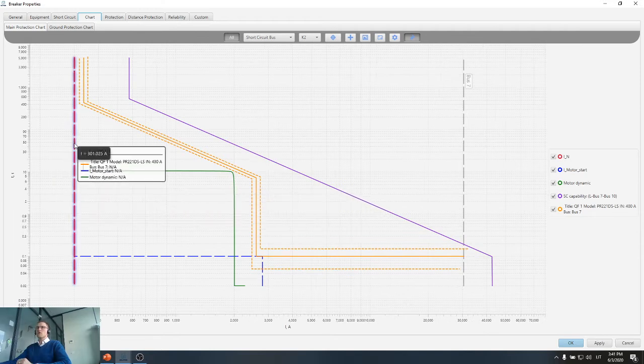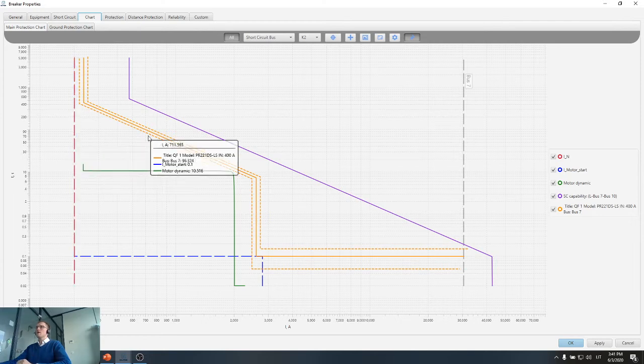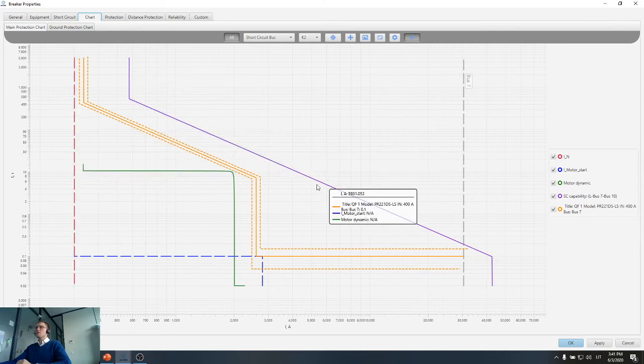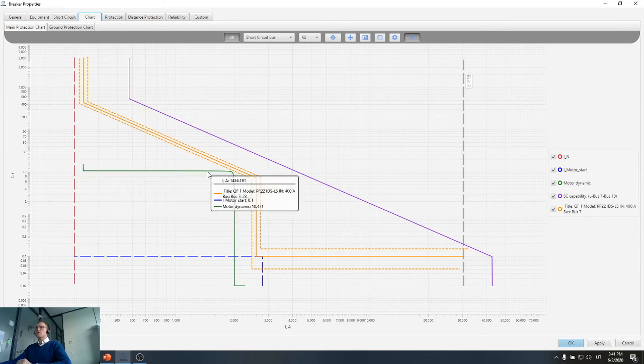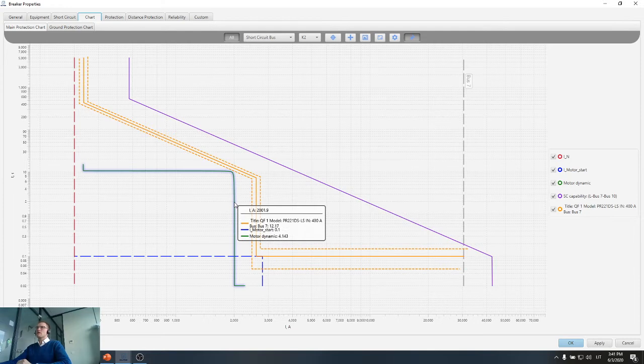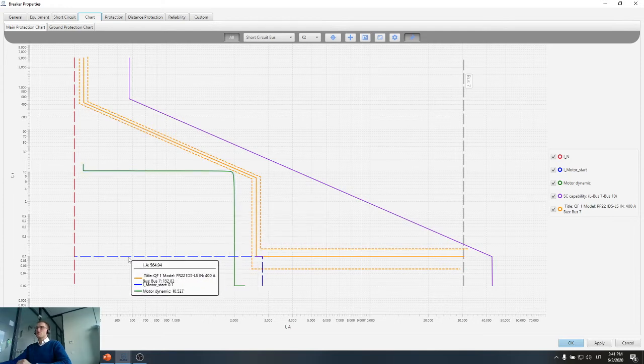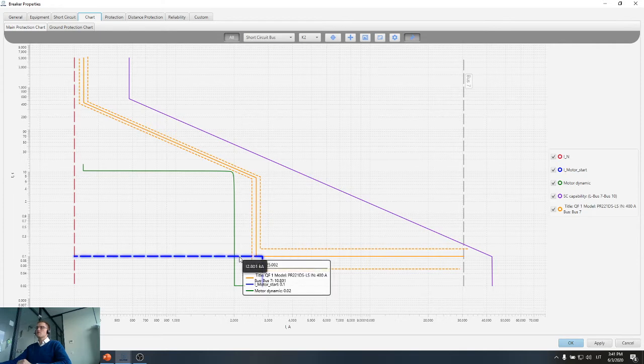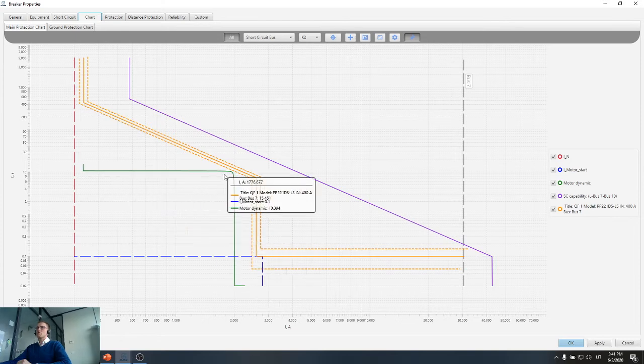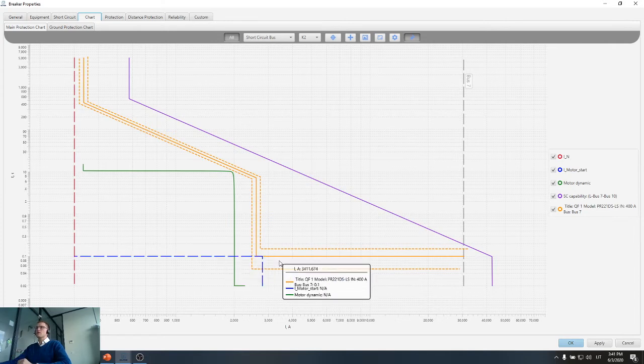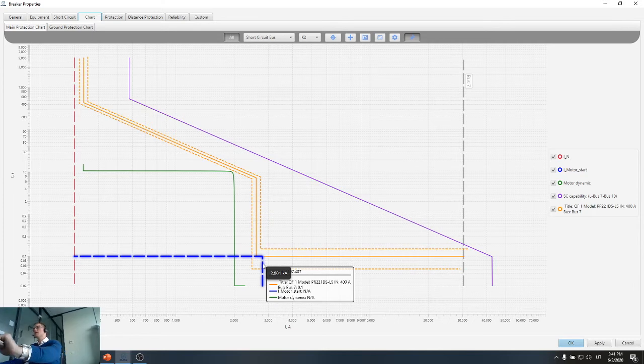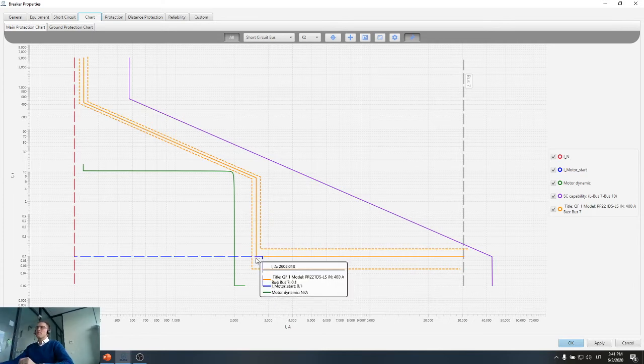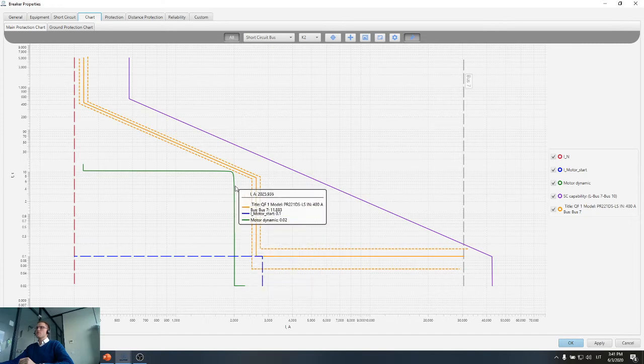What I see here, again, is a normal operation curve, which is 300 amps. Then I see information about the cable capability, and this green curve shows the motor starting time and also the motor starting current. The blue curve also shows motor starting time, however it's calculated with a different method. This is a simple motor starting, and here is dynamic motor starting. As I have mentioned, simple motor starting usually gives a more conservative current. It is a little bit bigger. However, it does not allow us to estimate motor starting time, so we don't know how long it will take for the motor to start.